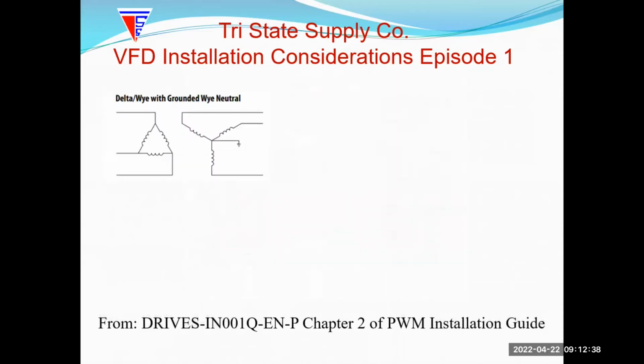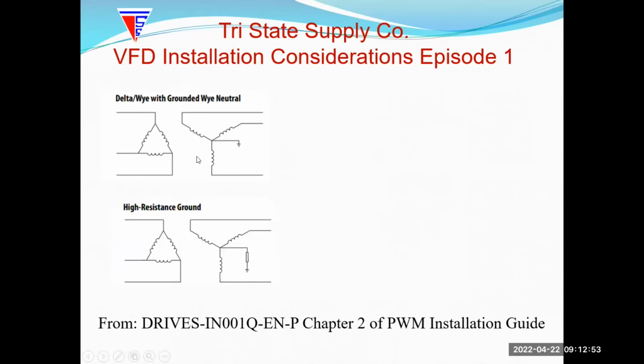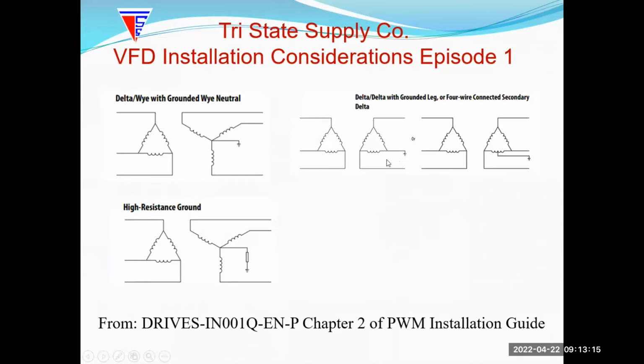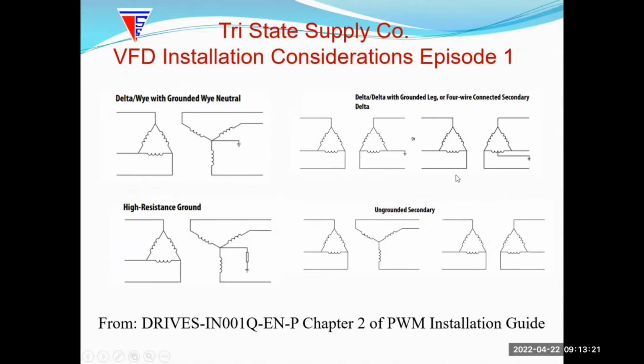So we go back to our transformer. There's several different configurations. Here are some of the more common ones. This is the one that the drive manufacturers recommend, a solidly grounded Y. Then you have your high resistance or resistant ground, which puts a resistor on that neutral, which is done a lot of times to reduce your ground fault currents for safety precautions. Then you can have a delta corner ground or center tap ground, or an ungrounded system altogether.